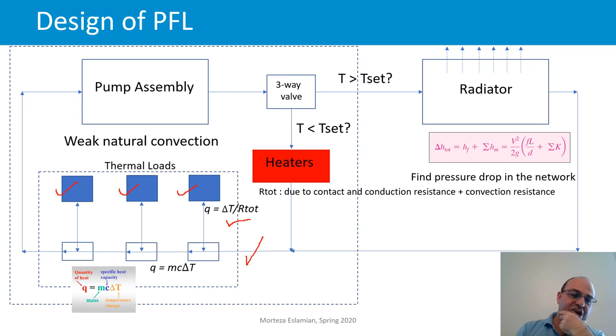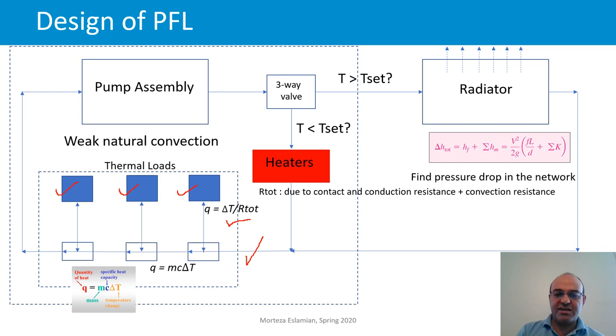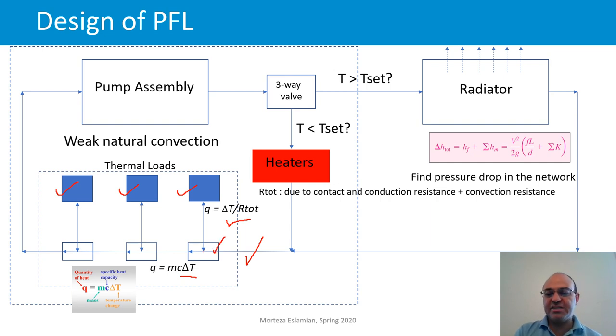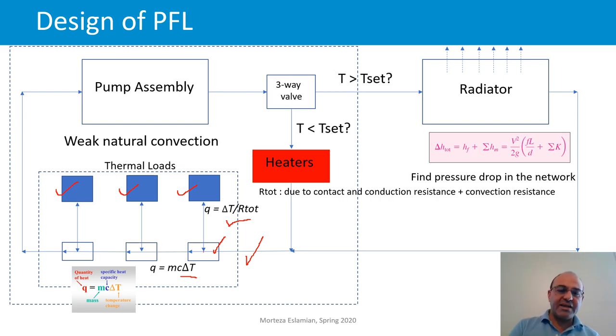The convection heat transfer is expressed as delta T divided by the total thermal resistance, which consists of conduction resistance through the tube walls and the convection resistance itself. As the fluid passes through each heat sink junction receiving heat Q, the temperature increase of the fluid is equal to Q divided by MC — the thermal capacitance of the fluid. The temperature change before and after each heat sink section is not substantial.